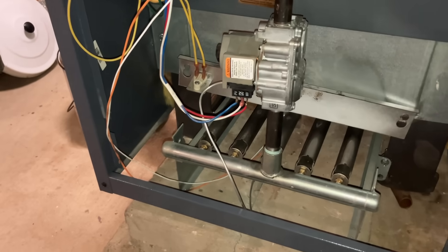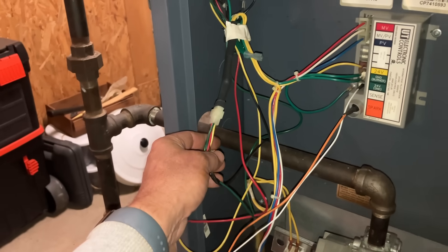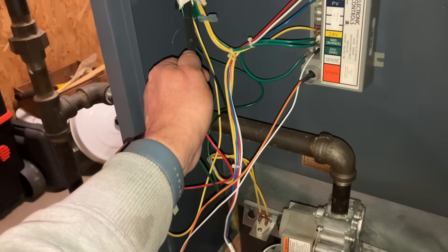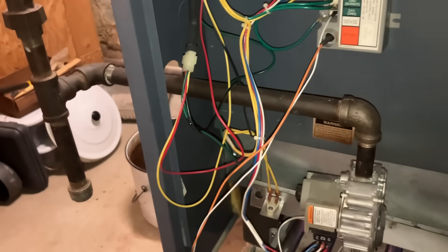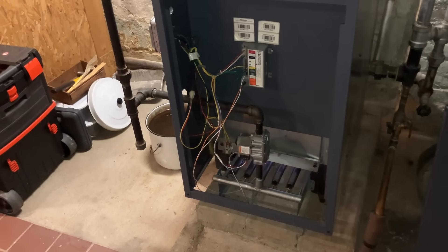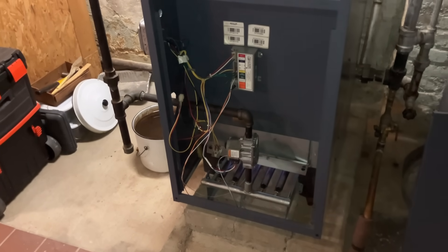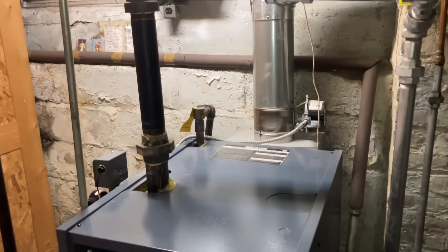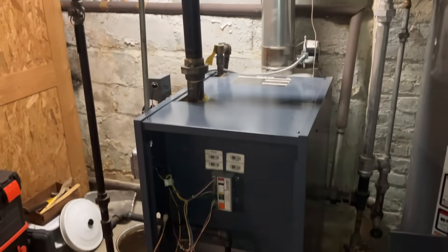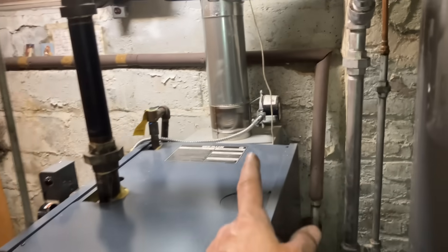I already put my head under the hood, and the harness for the vent damper assembly moved. That's very interesting — it further reinforces my belief that there's something up with the vent damper. Because it is New Year's Eve and we don't have a replacement damper available, we're going to electrically bypass the vent damper temporarily for the comfort of the property owner. But you have to replace the vent damper — this is only a temporary fix.